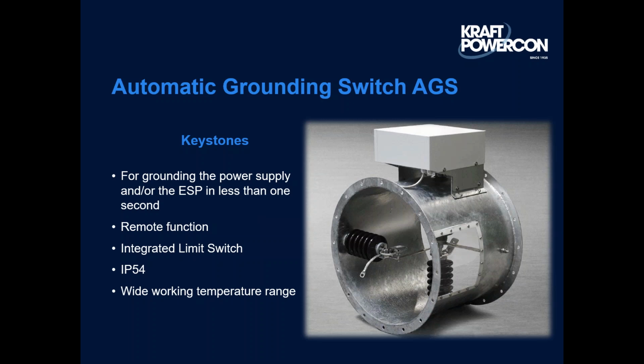What this ground switch does is, if there's a potential for combustibles in the precipitator, the ground switch is notified. It disconnects the TR set physically with an air gap and grounds the precipitator field within one second, discharging the capacitor so the ignition source is no longer there. The potential goes to zero.